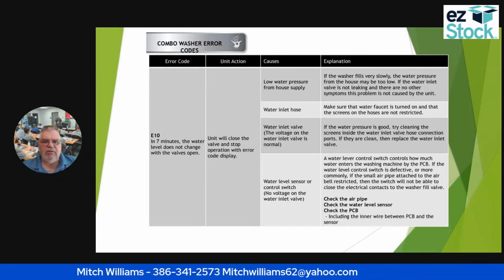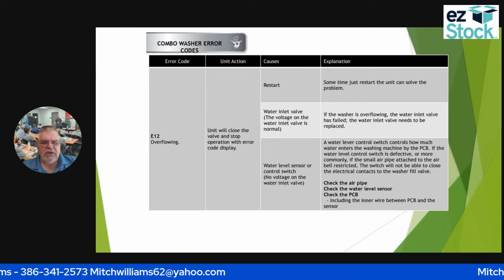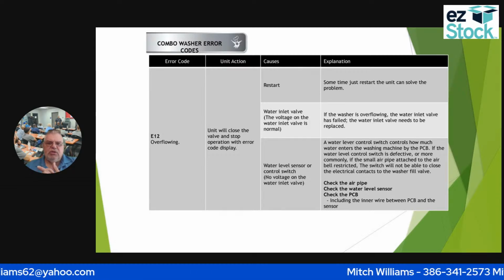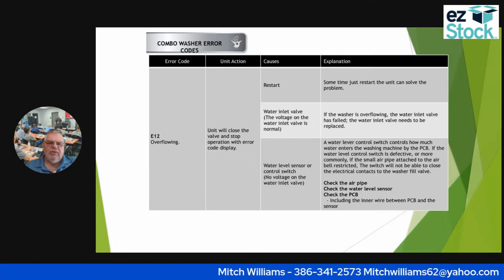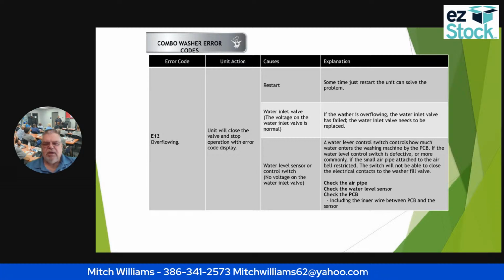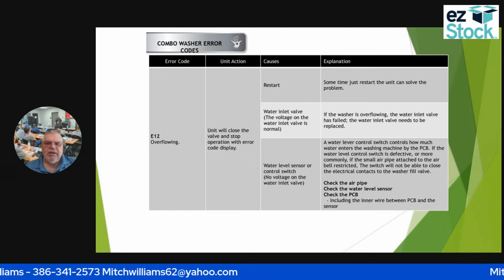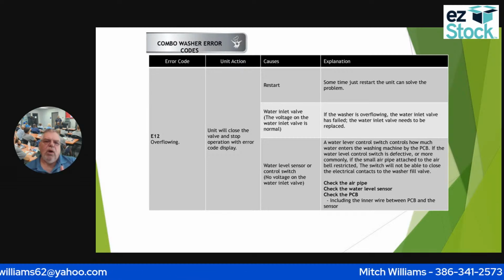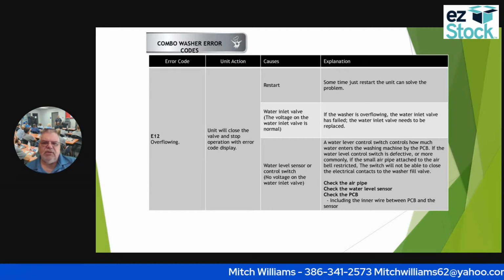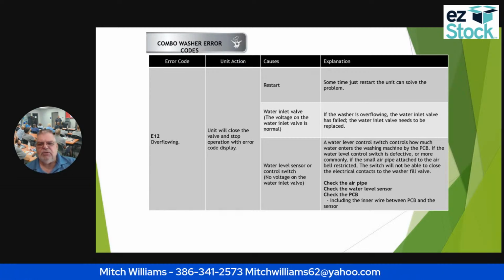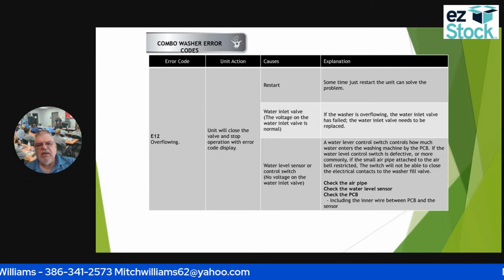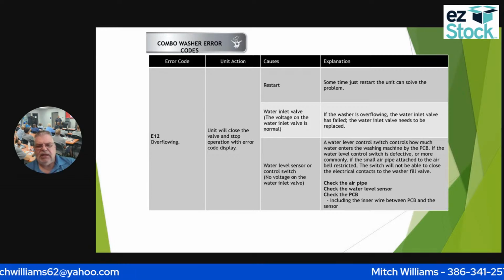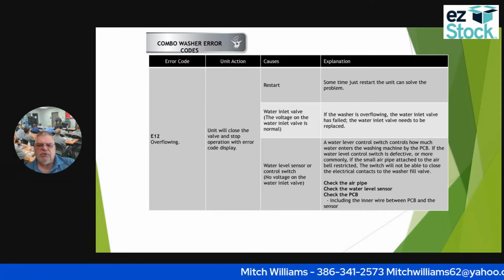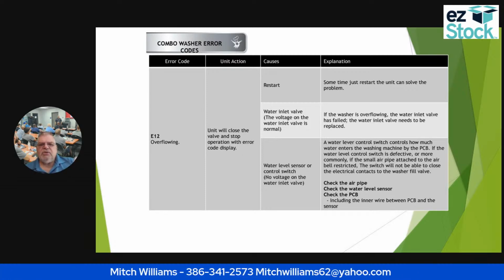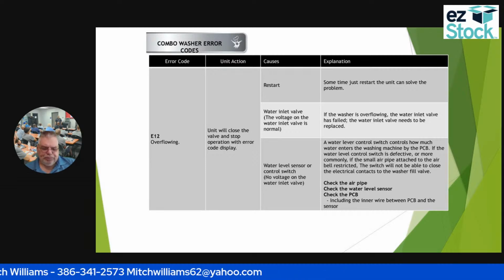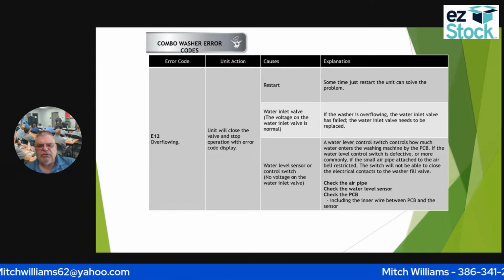There are other codes that are prevalent. One is an E12. That just tells me that the unit is overflowing. So the unit will close the valve and stop operation with the error code in the display after a while. It may take a little bit of time. So what are the causes of this? Sometimes all I have to do is restart the unit, and that'll solve the issue. I would tell you that's the last thing I'm going to be checking. The first thing I'm going to check is my water inlet valve.